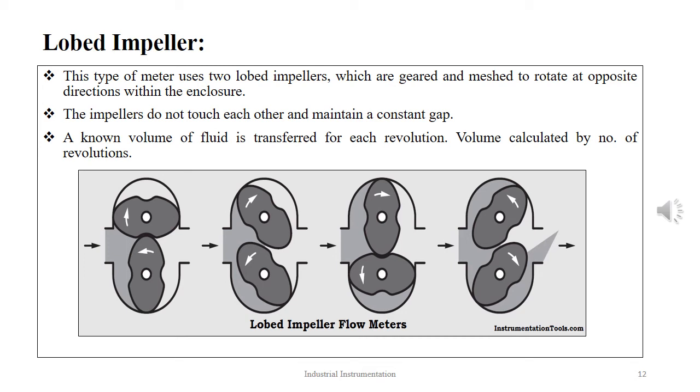During each rotation, four crescent-shaped volumes are moving through the closed cavity. A known volume of fluid is transferred for each revolution, and the volume is counted by knowing the revolution count.